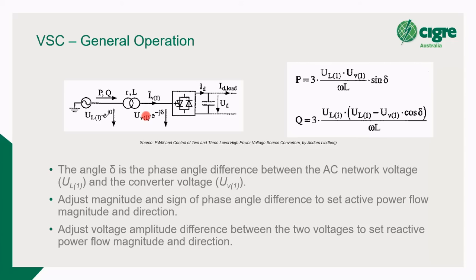Now, the reactive power doesn't flow in the DC lines, obviously, but what it means is each converter can independently control the reactive power flow in and out within the limits of the converter, but to a very good degree of granularity. And this is where that benefit comes in, which some companies call an SVC mode or a STATCOM mode. So even if you had a cable failure, you could still operate the converter and provide reactive power support to your network.